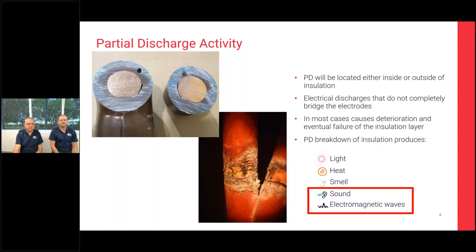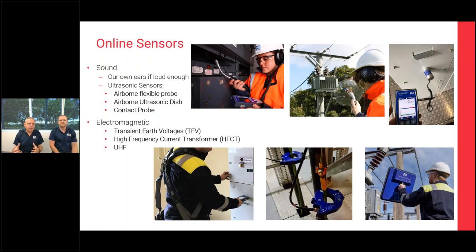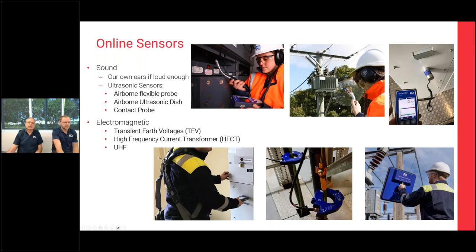You can use your own ears — if you go into a substation and hear crackling and fizzing, you're probably already in a dangerous state. What we're trying to do with our technology is find things before they get to that stage. We use ultrasonic techniques: flexible airborne sensors, parabolic dishes for distance work, and contact probes to listen through metalwork for ultrasonic surface-type discharge through a sealed chamber.